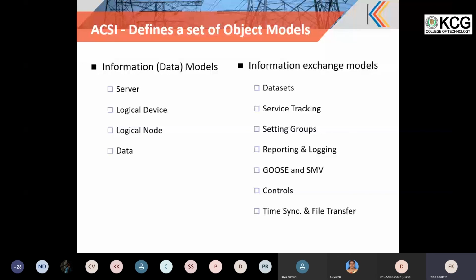A setting group is a group of data, and multiple groups of settings can be there, and you need to switch between them. For example, if the frequency is around 50, you can use one group of settings, and if it goes below 49, you want another group of settings to be applied, and if it goes further down to 48, you want another group of settings to be applied. That is done using the setting group.